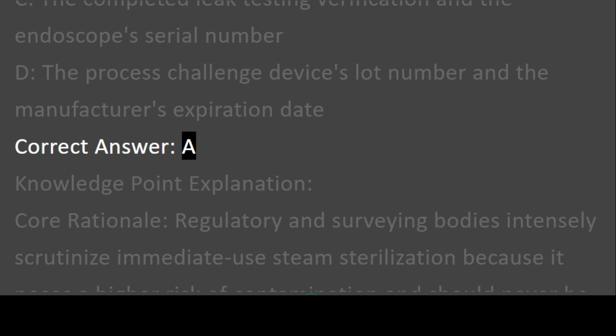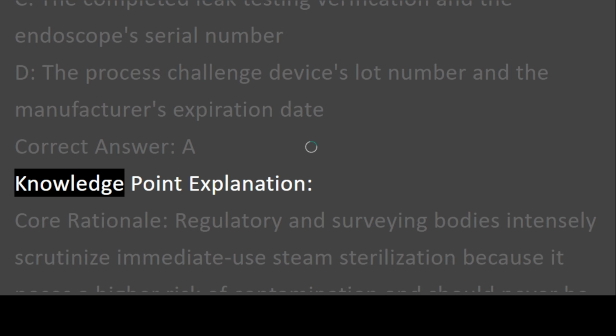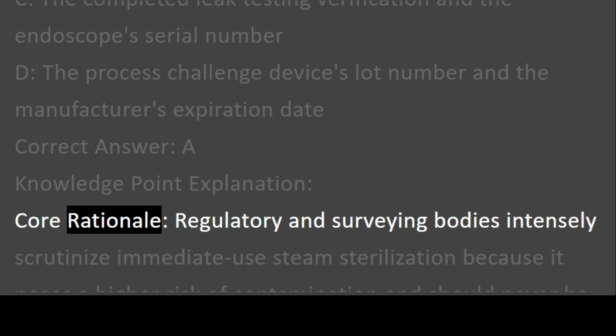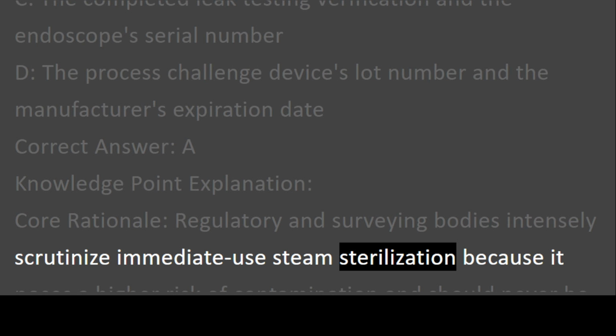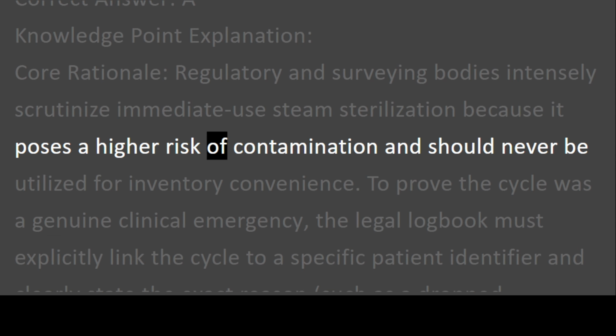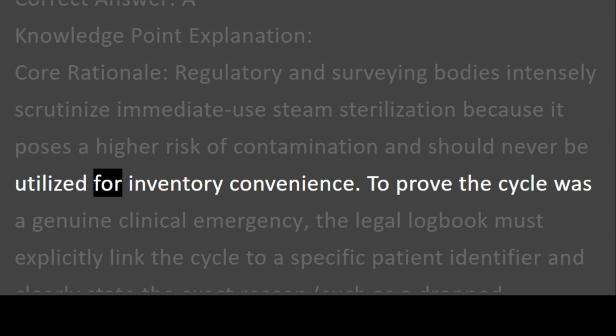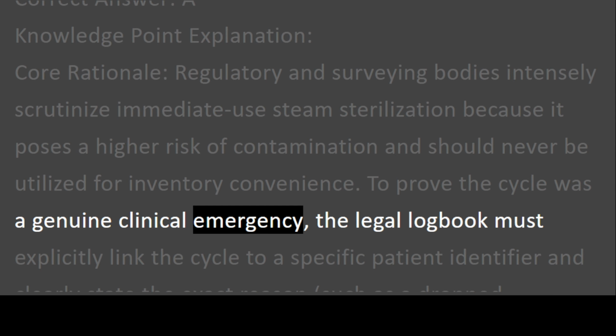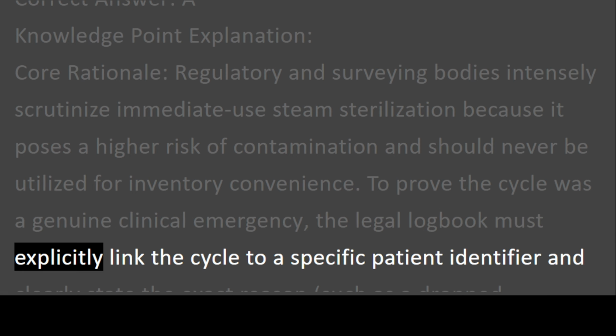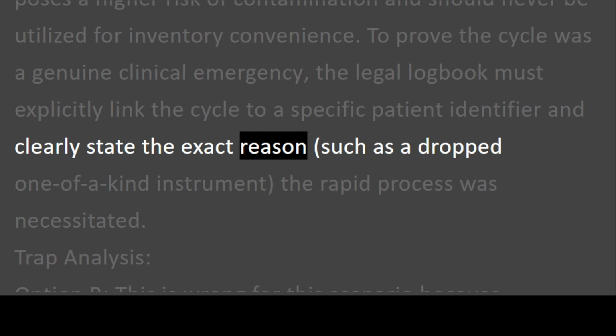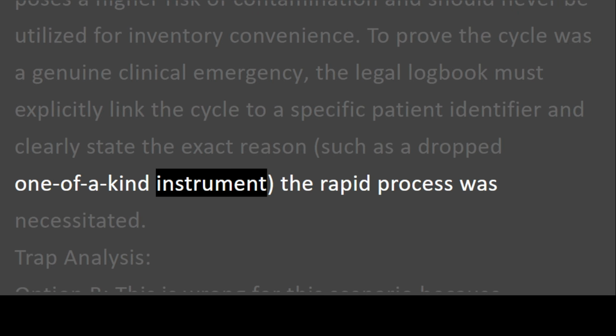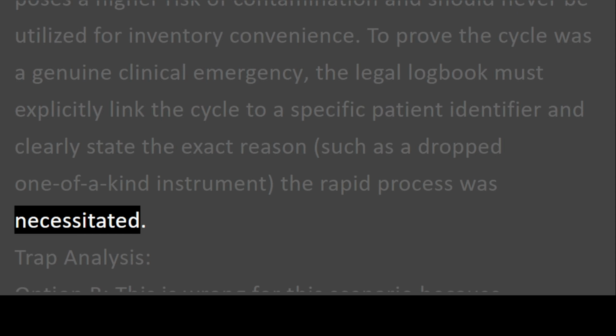Correct answer, A. Knowledge point explanation. Core rationale. Regulatory and surveying bodies intensely scrutinize immediate use steam sterilization because it poses a higher risk of contamination and should never be utilized for inventory convenience. To prove the cycle was a genuine clinical emergency, the legal logbook must explicitly link the cycle to a specific patient identifier and clearly state the exact reason, such as a dropped one-of-a-kind instrument, that necessitated the rapid process.